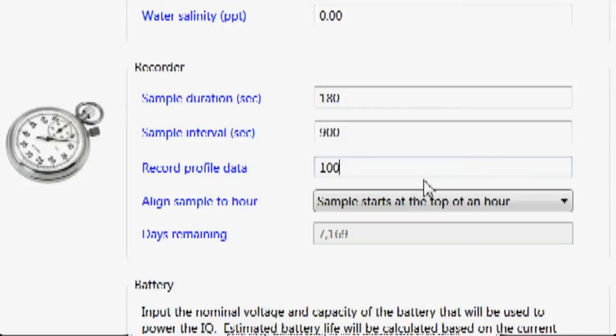If you're not planning on recalculating flow, or if you have everything set up to do flow automatically, typically you will want to set this value to 100 or maybe even larger. If you set it to zero, no recalculation would be possible. In that case, you would significantly save on recorder space, the time for download, and all that.